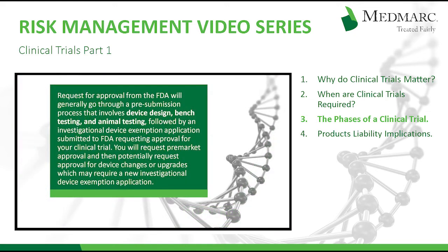Request for approval from the FDA will generally go through a pre-submission process that involves device design, bench testing, and animal testing, followed by an investigational device exemption application submitted to the FDA requesting approval for your clinical trial. You will request pre-market approval and then potentially request approval for device changes or upgrades, which may require a new investigational device exemption application.